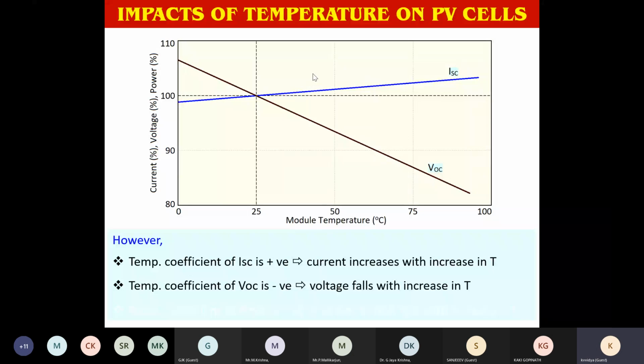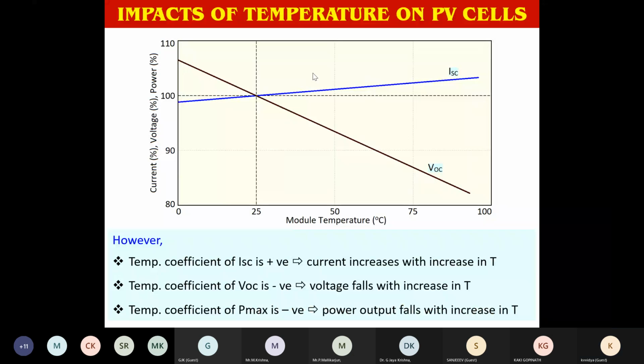The combined effect of current and voltage gives power, and the fall in power will be much steeper. Notice this dP by dt, that is, for an incremental change in temperature, what is the drop in power. These three parameters are given in the data sheet as the temperature performance coefficient, showing how current and voltage perform as temperature increases. What we are bothered about is this value; for a good module, it should be as minimum as possible.